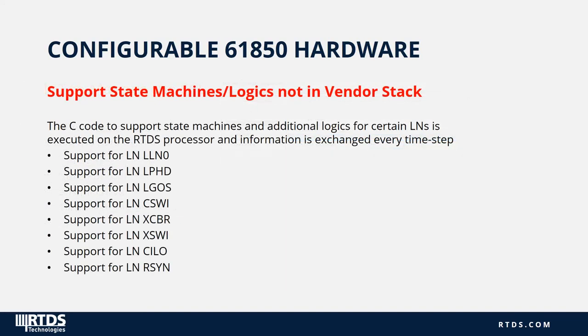Support for state machines and logics that are not in the vendor stack was implemented in the hardware. The C code to support these state machines and additional logics for certain logical nodes is executed on the RTDS processor and information is exchanged every time step. There is support for logical nodes LLN0, LPHD, LGOS, CSWI, XCBR, XSWI, CILO, and RSYN.